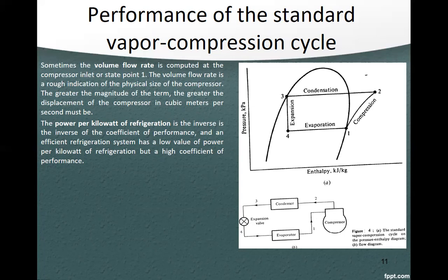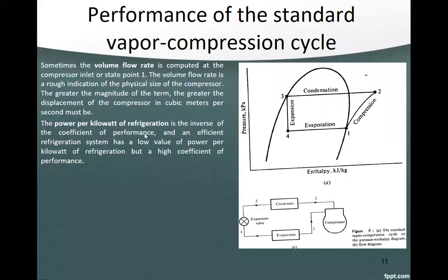And another performance measure is the power per kilowatt of refrigeration, which is the inverse of the coefficient of performance. An efficient refrigeration system has a low value of power per kilowatt of refrigeration, but a high coefficient of performance.